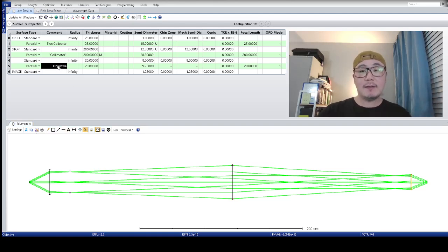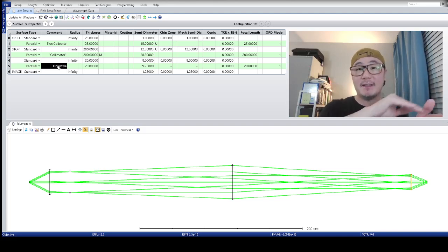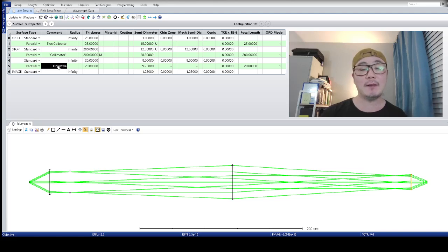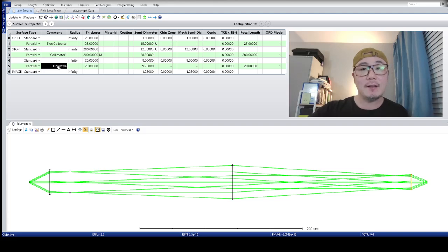Why? Because this whole system of lenses here represents a thin lens paraxial layout of a typical fluorescence microscope in the excitation path. Fluorescence is what happens if you shine light onto an object and the object is fluorescent, then it absorbs the light and emits light at a longer wavelength. That's fluorescence. The light that is being emitted is fluorescent light, or just the emitted fluorescence. So in a fluorescence microscope, you usually have an exciter, which is the system that you see here, and then you collect the emitted light in what's called the return path, right?